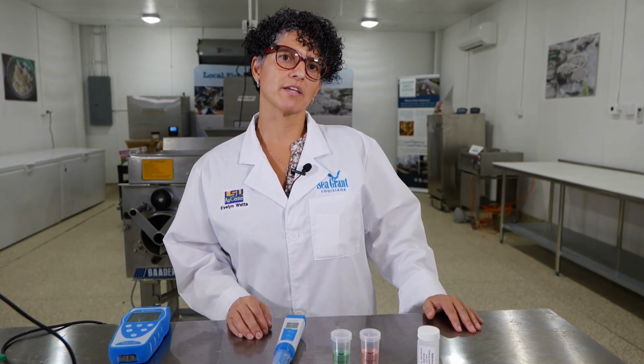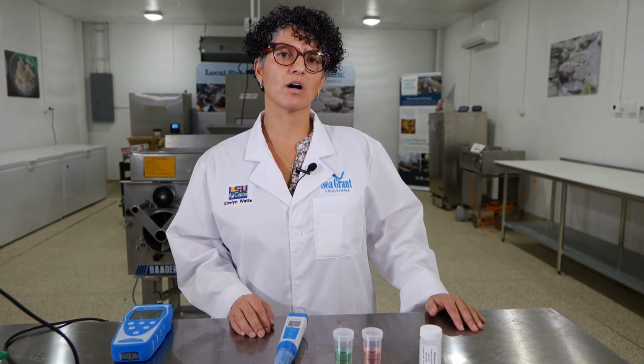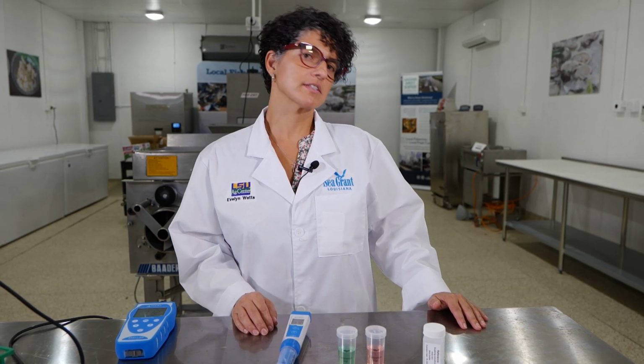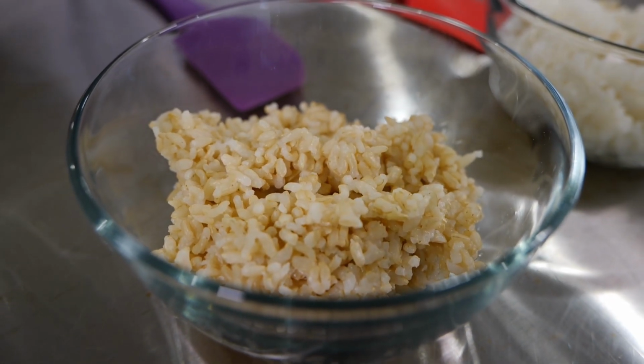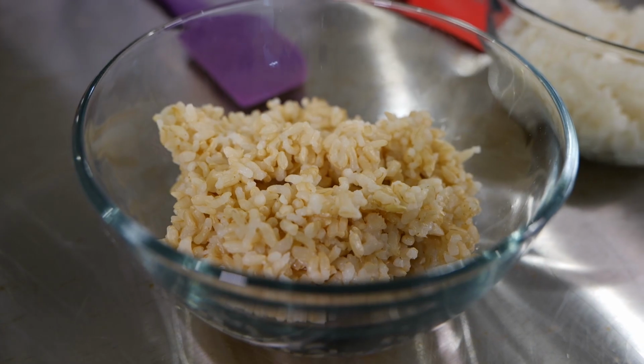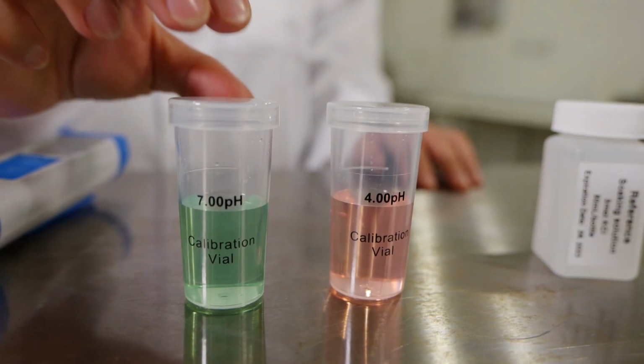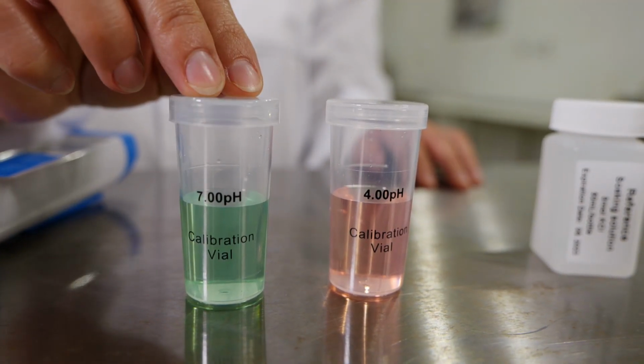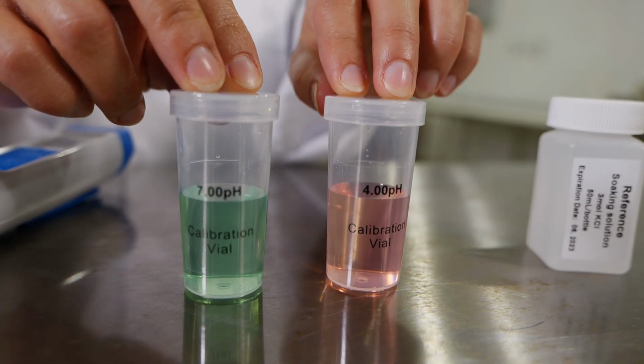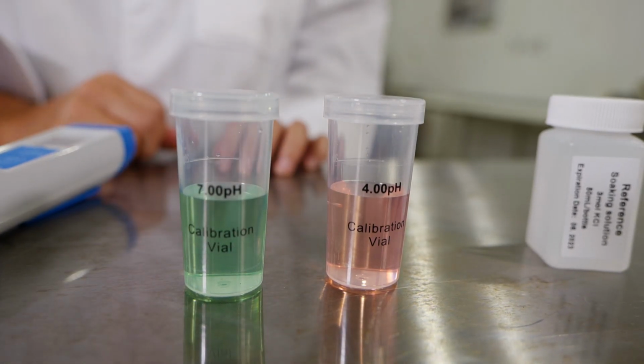When you are calibrating, it is important that you remember that you will calibrate within the range that you are going to be measuring. For example, if you were going to measure the pH of a sushi rice that is a low pH, then you want to use your buffer solution of 7 and 4. Some pH meters allow you for a 2-point calibration or a 3-point calibration.